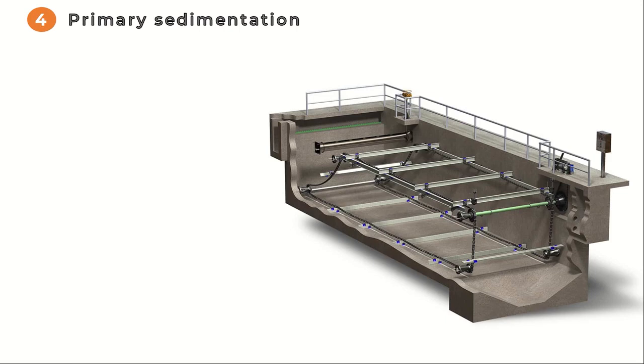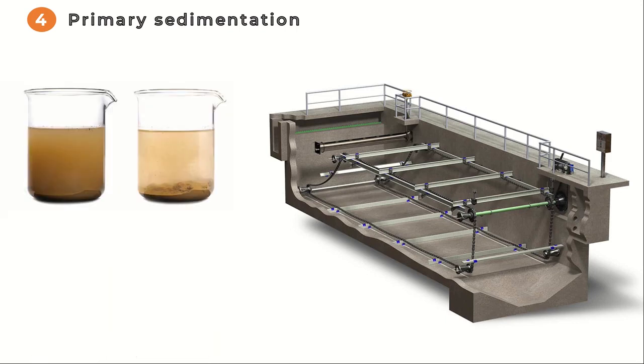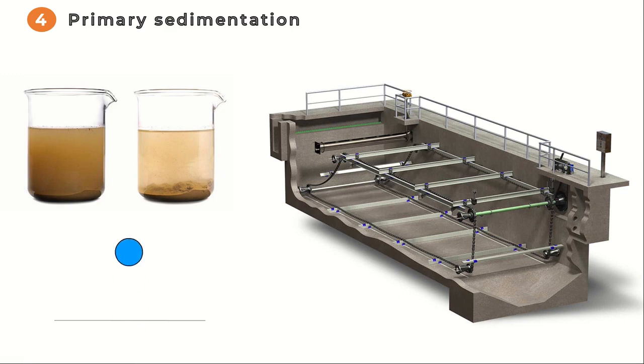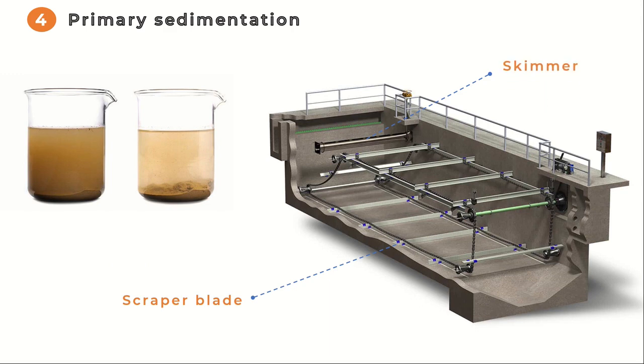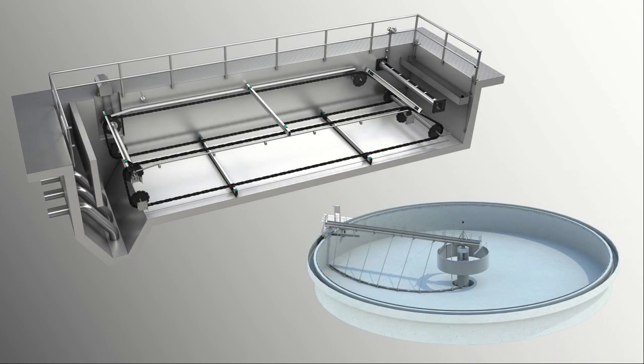The fourth step is primary sedimentation. The wastewater is transferred to large tanks where suspended solids and organic matter settle to the bottom due to gravity. The settled solids, called primary sludge, are removed for further treatment, while the partially clarified wastewater moves on to the next stage. Primary sedimentation tanks also contain equipment to remove floating solids and greases from the surface. Two common configurations are rectangular and circular.